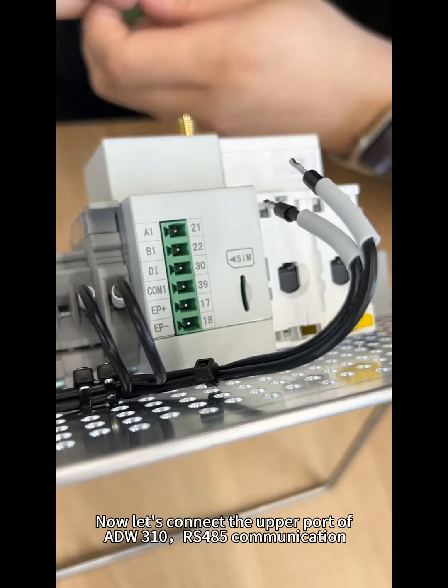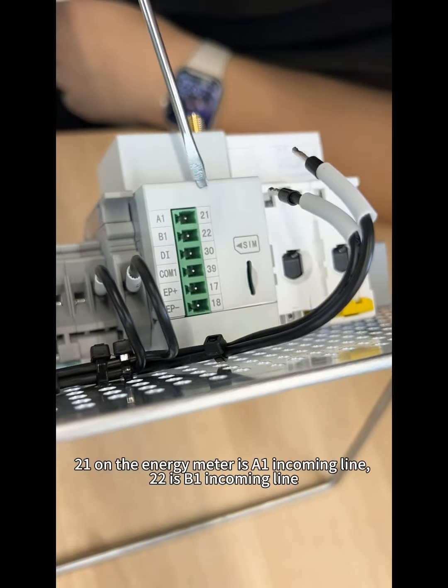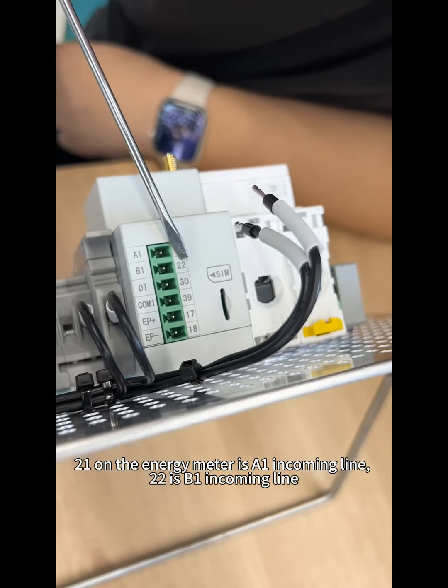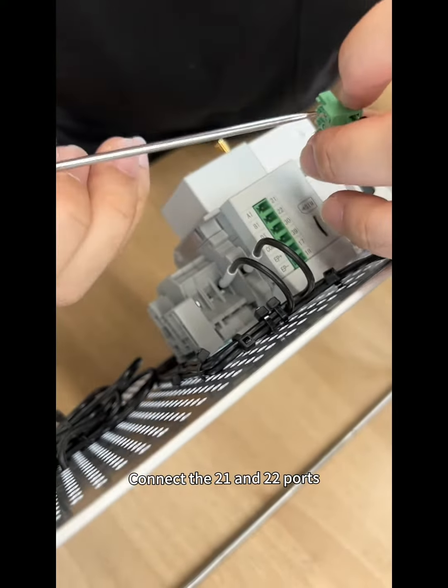Now let's connect the upper port of the ADW310 on RS485 communication. Port 21 on the energy meter is the A1 incoming line, and port 22 is the B1 incoming line. Connect the 21 and 22 ports.